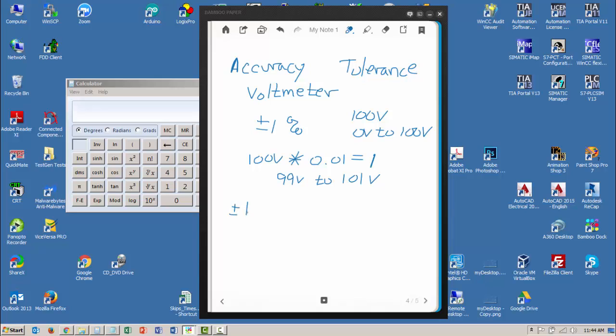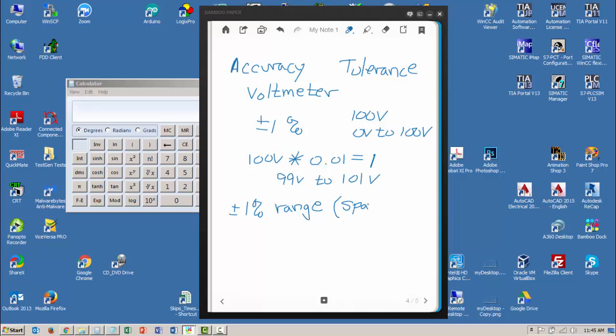minus 1% of the range. Well, plus or minus 1% of the range. Now this term 'range' might be a little confusing because I had told you that range is two values, and it still is—my range is 0 to 100 volts. So I could easily say 'span' here because I want to make sure it covers this range. So it's 1% of the range; my upper end is 100 volts.